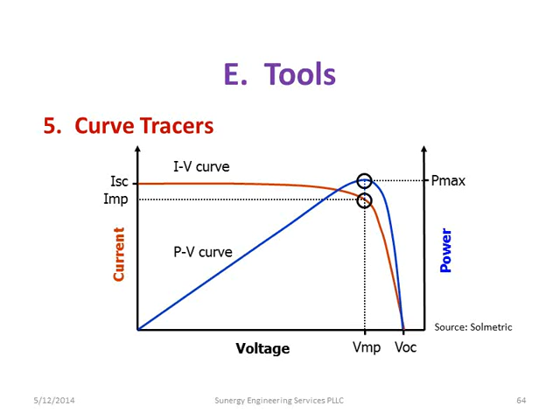Now let's talk about curve tracers. Like I said before, if you have the ISC, the VOC, and the VMP - the operating point, or knee of the curve - you should be able to tell if everything's okay with your modules. What the curve tracer does is give you more information for troubleshooting. Here's your normal curve in red.